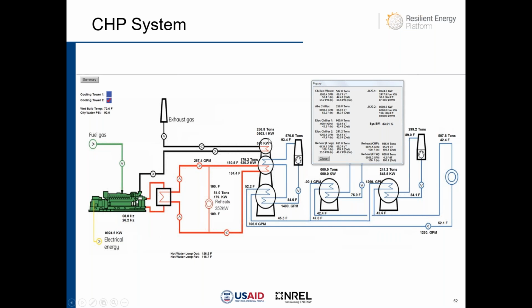So the exhaust gas is diverted to an absorption chiller, and the high temperature jacket water is also diverted to the absorption chiller. With those two, that heat is converted to a maximum capacity of 350 tons when the plant is operating at maximum capacity. And the low-grade heat from the second stage intercooler goes through a heat exchanger on the reheat loop, as I indicated. The electric chillers are in series, and this is an advantage because the thermodynamic process occurring in the absorption chiller is slow, and the electric chiller will make the fast response needed by the hospital.